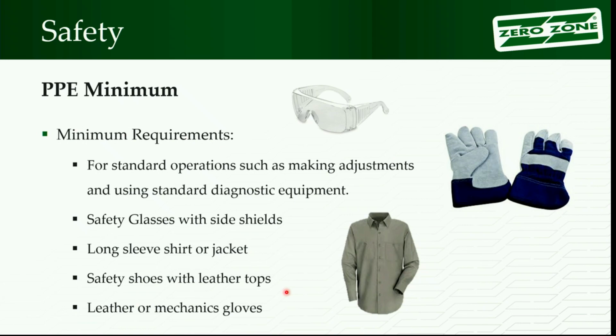Another item before I get into the PPE items you have to think about is where's your body in relationship to when you're working on the components. It's kind of like the safety valves. Where's my head in relationship to the discharge of the safety valve? But where's my face? If I'm taking a valve apart or doing some work on it, taking a cap off a Schrader valve, do you want to have your face looking over the top of that in case that Schrader valve cap blows off? Probably not a good thing, right? You want to be standing back. Same thing for the center mass of your body, right? That's where your vital organs are. If I can be working on higher pressure things, working to the side of my body versus right in the middle of my body is a better thing.